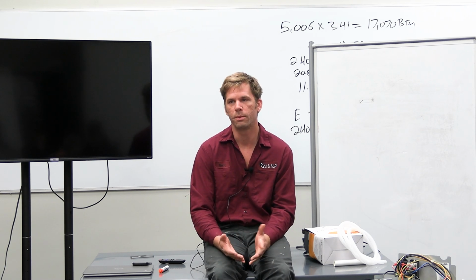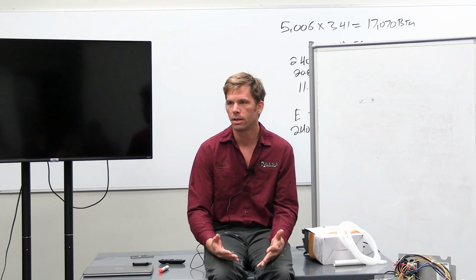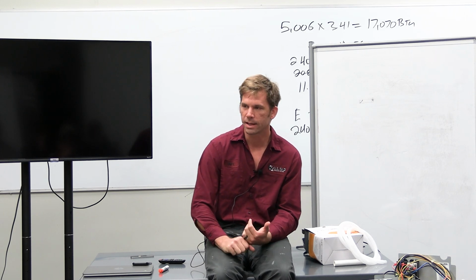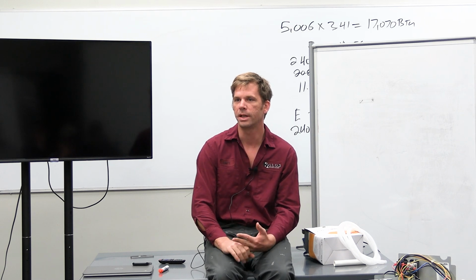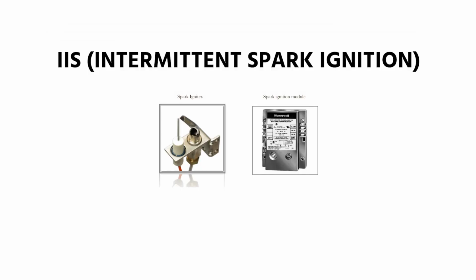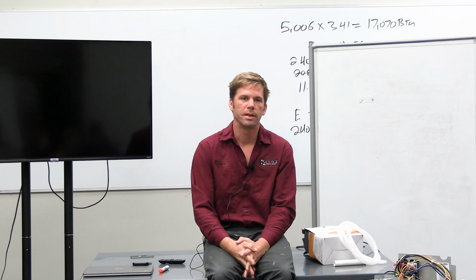So when you get an error code that we haven't been lighting, there are a few things you want to check. Do I have gas supplied to my heater? And is my igniter actually glowing red hot? Some of the older heaters have a spark igniter, and so you will hear that trying to spark as soon as it gets that call. What it does is it lights a little pilot light. There's a little tiny tube coming from your gas valve, a flame sensor, spark igniter, all right there. It lights a little pilot light, and once it senses flame from that little pilot light, then it will open the gas valve. So same thing with the igniter.